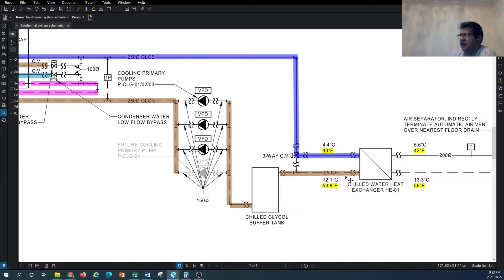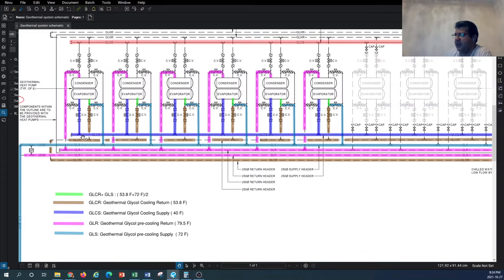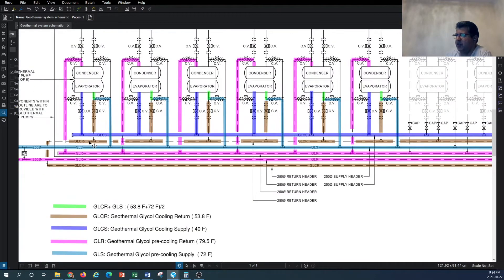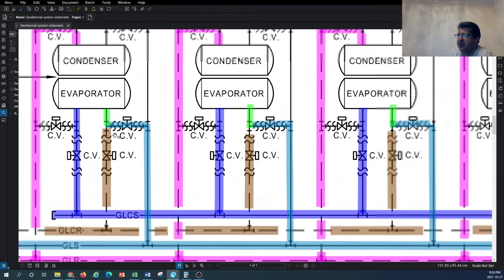If the return temperature is too high or too low, we blend it in the buffer tank to meet the chilled return requirement. We also have three pumps recirculating the chilled glycol back. As you can see, there is a reverse-return piping arrangement here, and the chilled glycol comes back and is redistributed back into the evaporator side of the geothermal heat pumps.